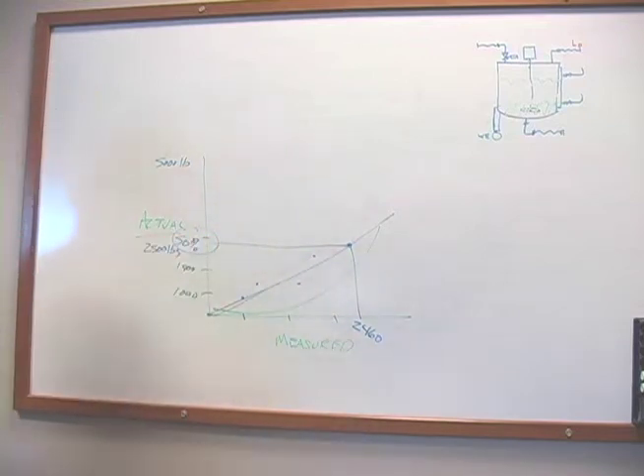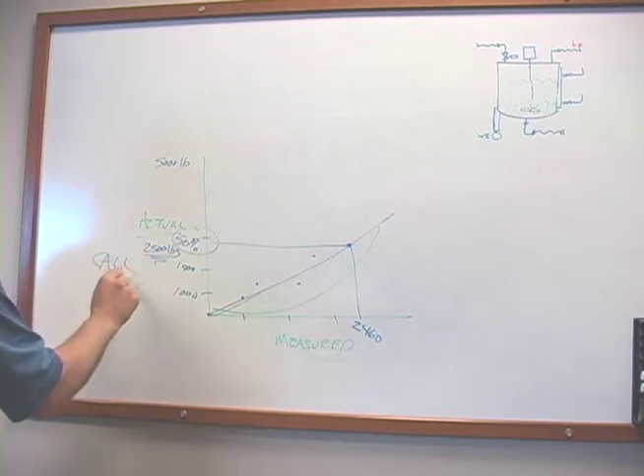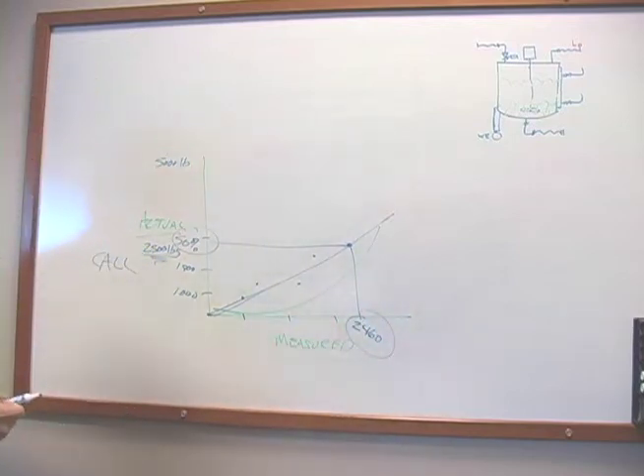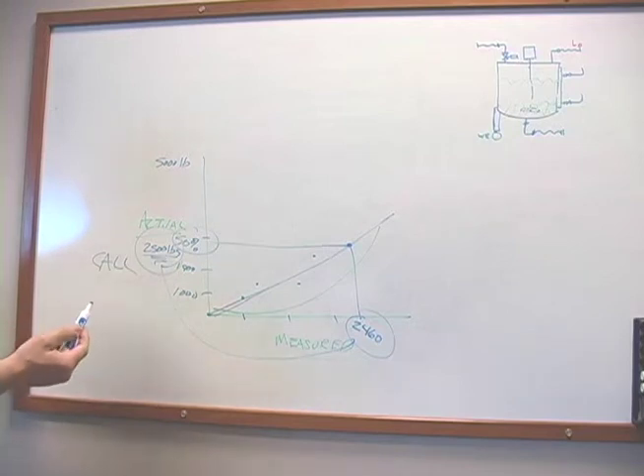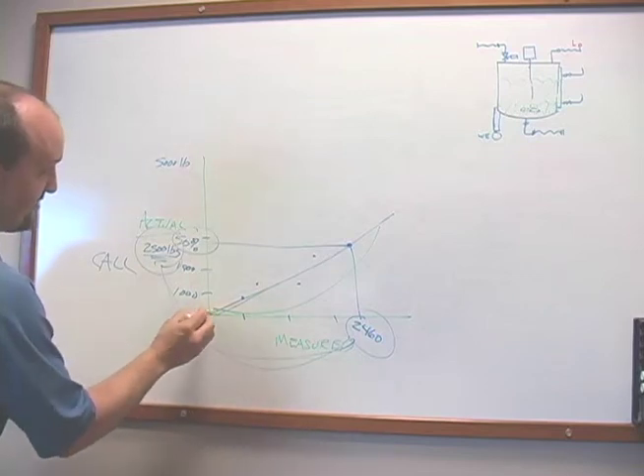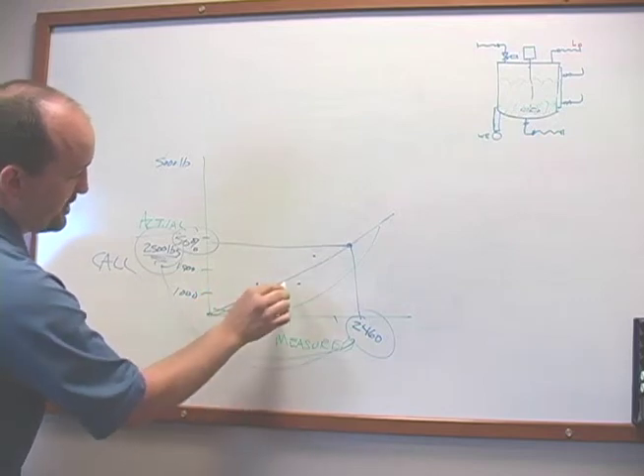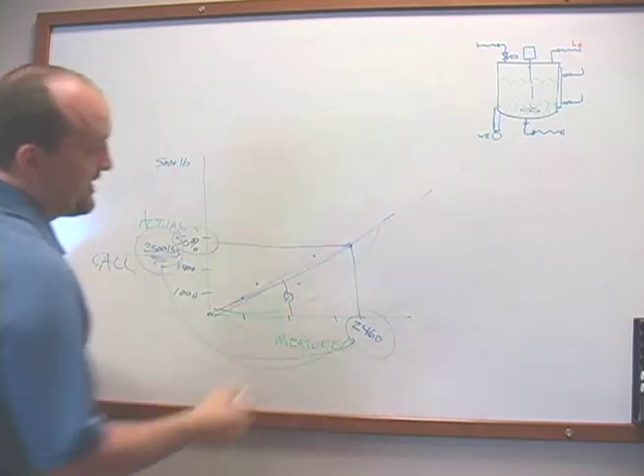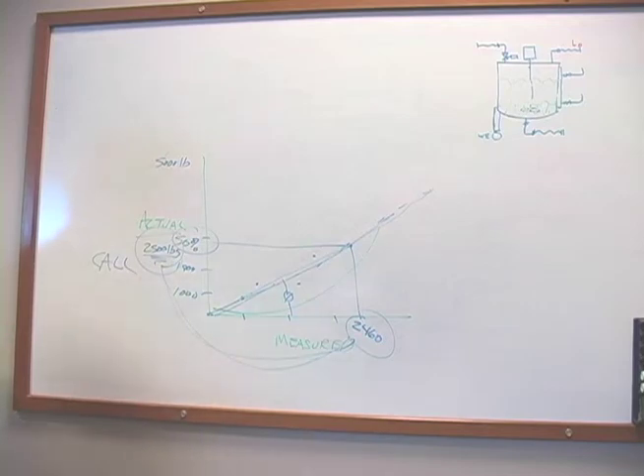So very simply with that 2,500 fixed pounds in the tank, you go to calibrate and you enter. It will say it's currently at 2,460 and you say, no, it's at 2,500. System now knows, oh, that is my calibration factor. And in effect, what it does then is it moves this line or changes the angle of that line to match that. Now, everything along it is more accurate. That's as simple as calibration is.